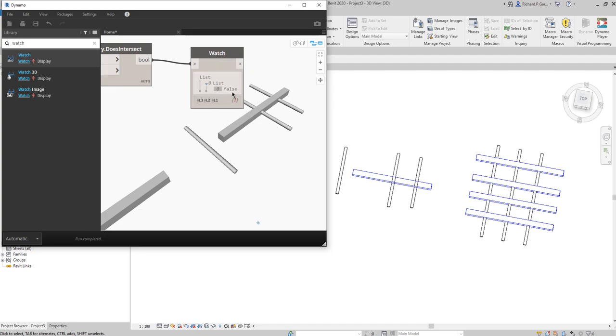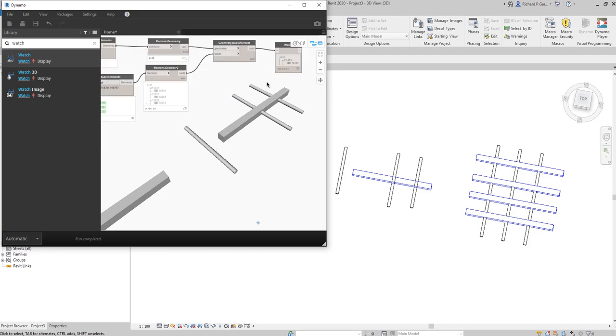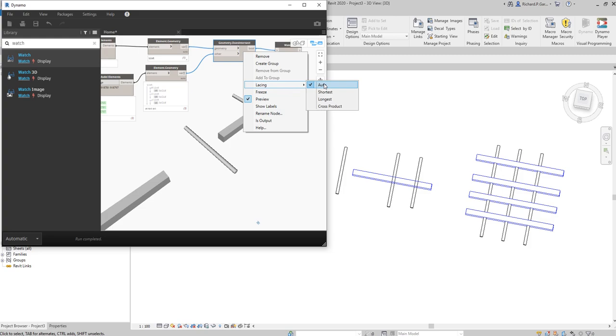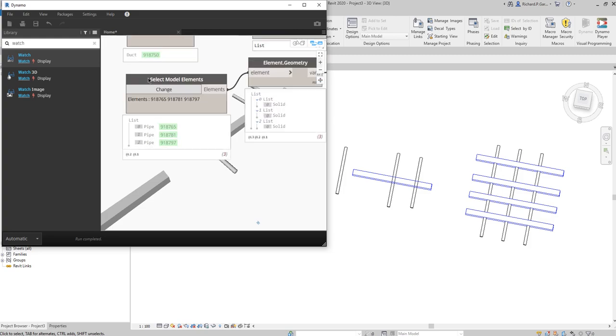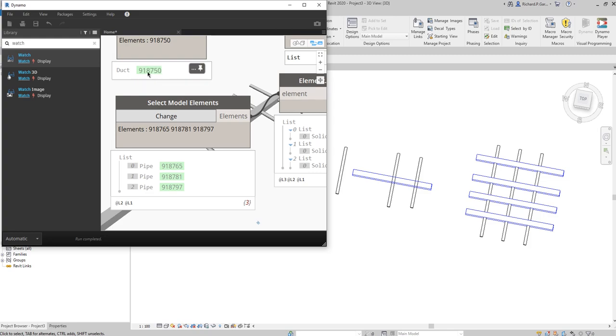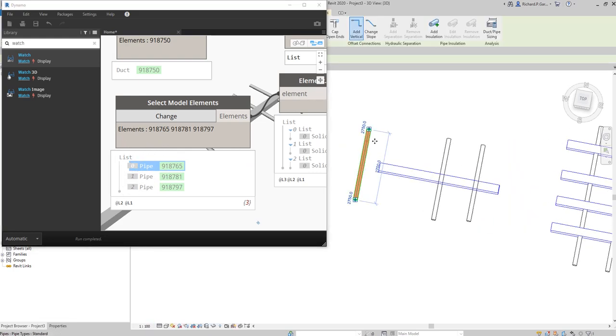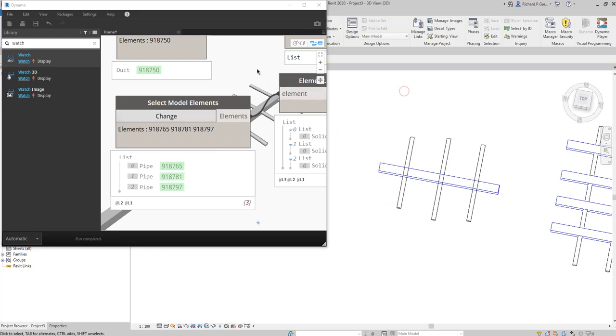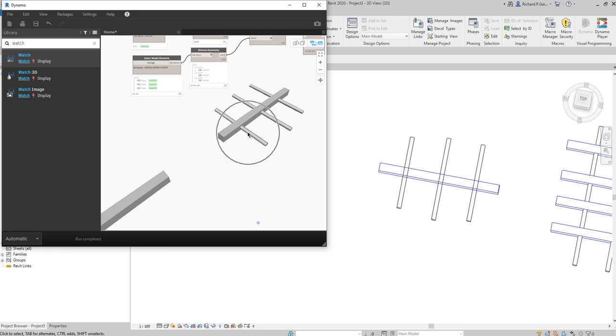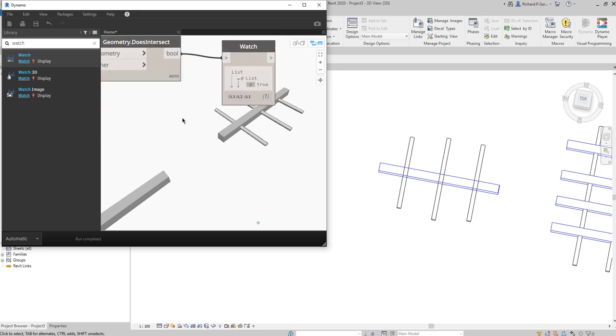So we confirmed that with lacing set to Auto or Shortest, Dynamo checks the intersection between the duct and only the zero-index pipe. I'll go back to Revit and move the pipe back into the duct, and again it automatically updates to true.